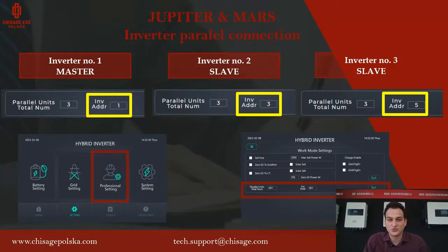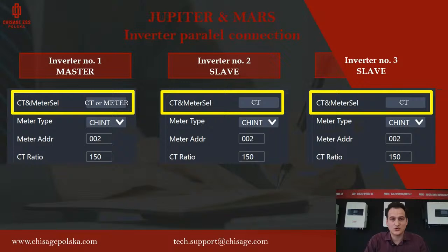On this inverter, we have to choose all the settings. This inverter will manage the whole installation. So the next thing we have to do is go to grid settings, and we have to pick the measurement. For the master, we pick the real measurement. So if we have CT, we pick CT. If we have a meter, we pick meter. So for the master, we pick what we have. For the slave inverters, we have to pick CT all the time. So for any slave inverter, we go to CT.